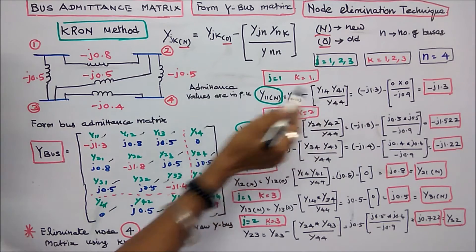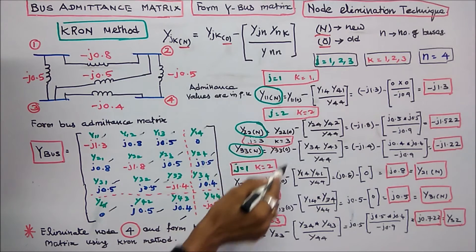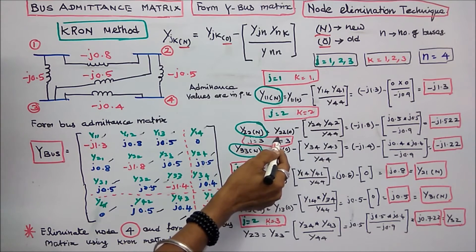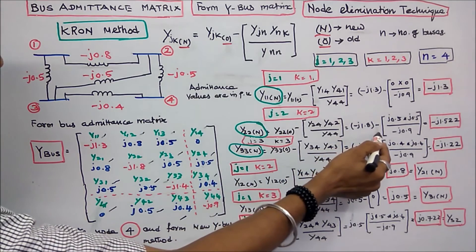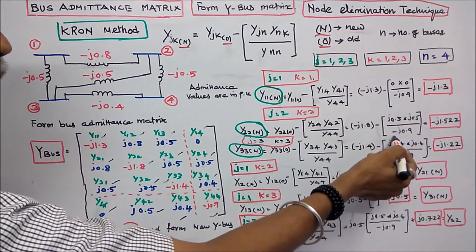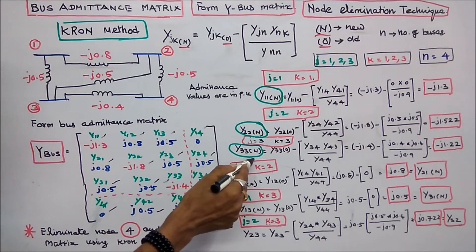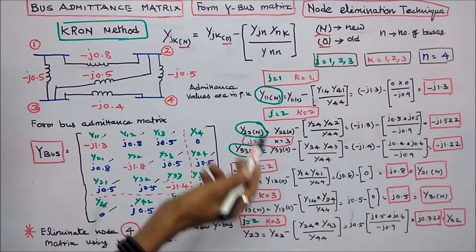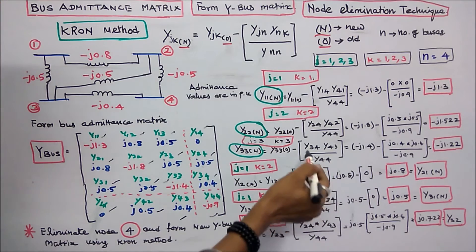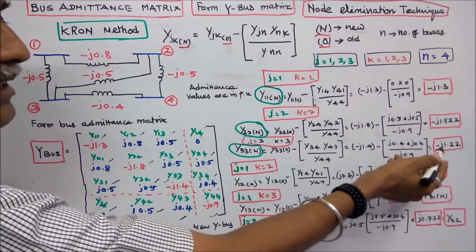For j=2, k=2: Y22(new) = Y22(old) minus Y24 times Y42 divided by Y44. Y22(old) is minus j1.8, Y24 is plus j0.5, Y42 is plus j0.5, and Y44 is minus j0.9. This gives minus j1.8 minus (j0.5 times j0.5 divided by minus j0.9), equaling minus j1.522. For Y33(new): Y33(old) is minus j1.4, minus Y34 times Y43 divided by Y44, which is j0.4 times j0.4 divided by minus j0.9, giving minus j1.22.